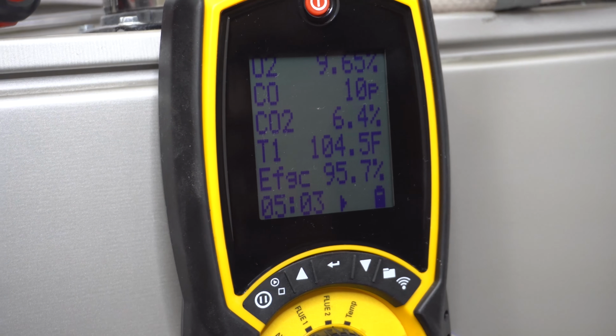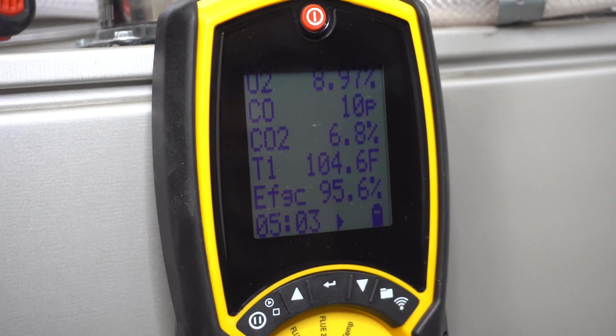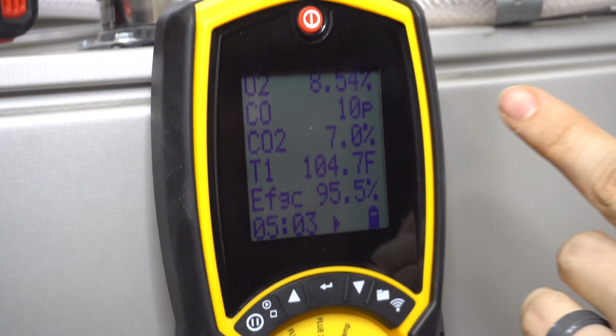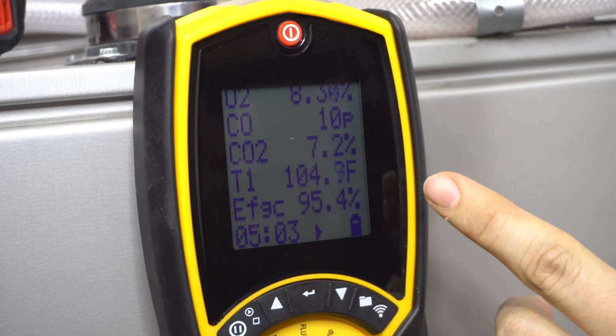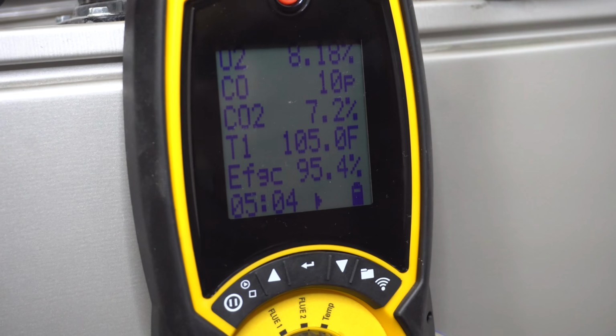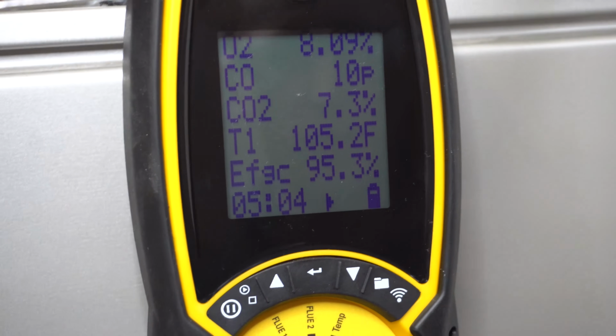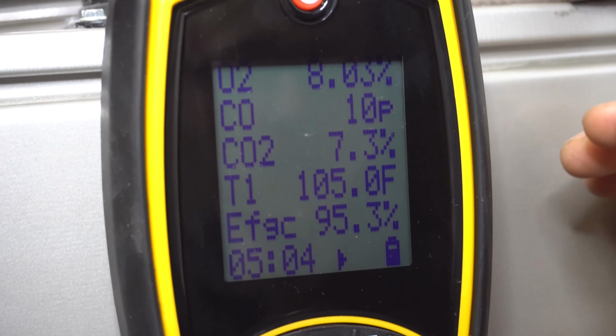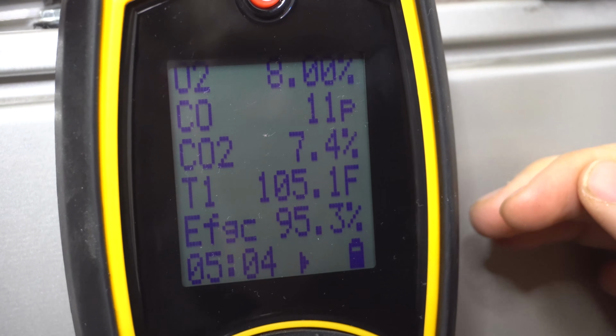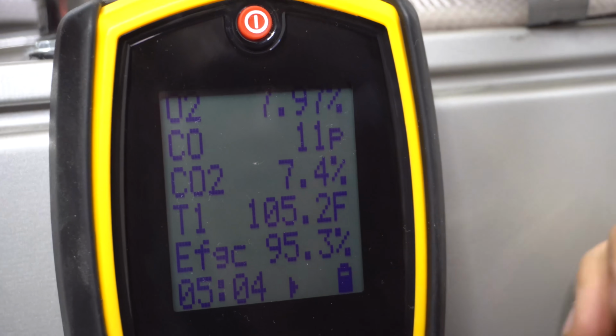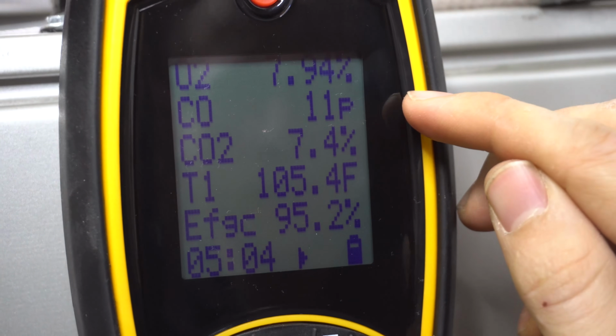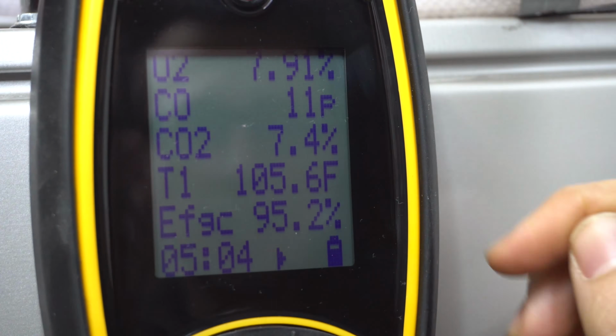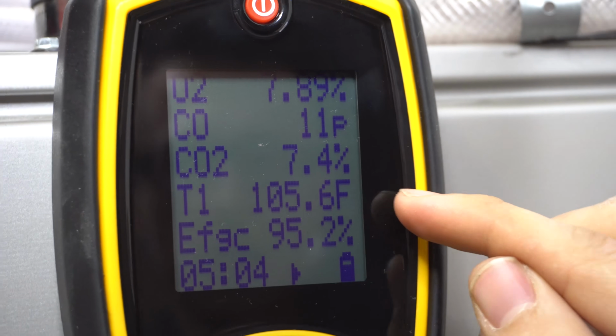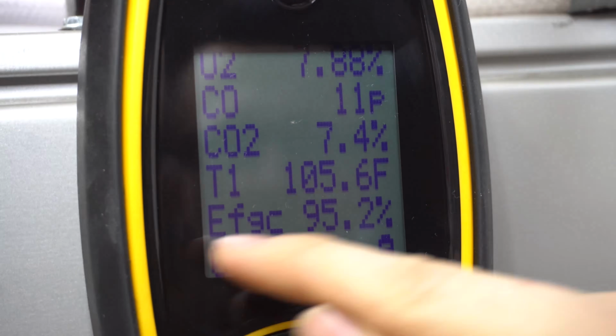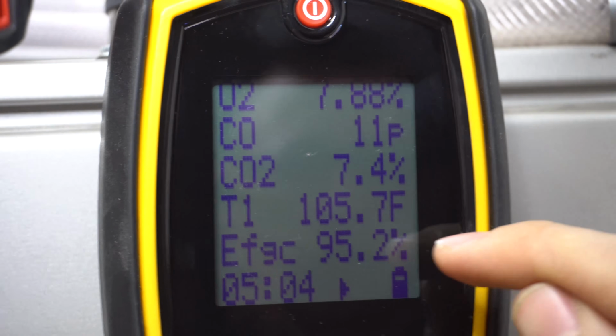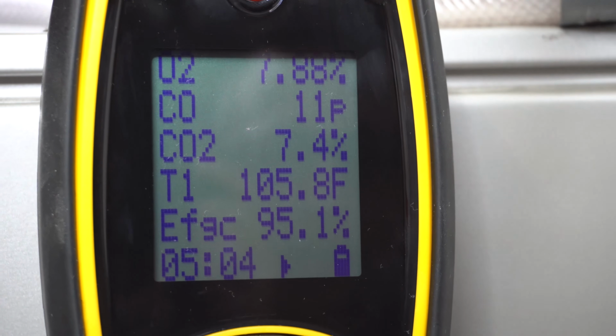Okay, so the furnace finally kicked into high stage. And as you can see, the numbers are starting to change now. Now that the gas pressure has gone up, the inducer motor has gone up in speed as well. Let's see how this affects our numbers here. So the oxygen is going down, carbon monoxide is slowly going up, the carbon dioxide is slowly going up as well, along with the temperature, and our efficiency dropped a little bit when we kicked into high stage.